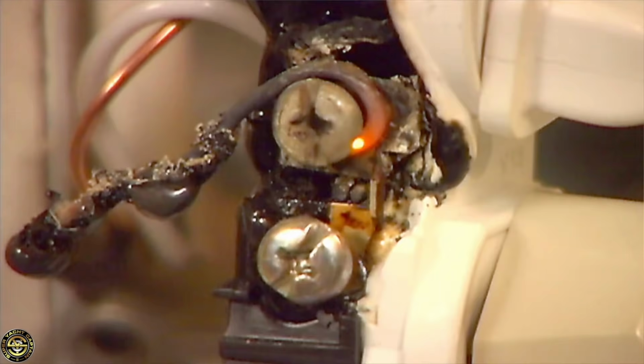So what can cause the insulation to fail? So excessive heat. So maybe an electric motor is overheating constantly and it can actually cause the insulation to dry and crack and fail. Mechanical vibrations can also cause it to fail over time. Mechanical damage, maybe an impact.